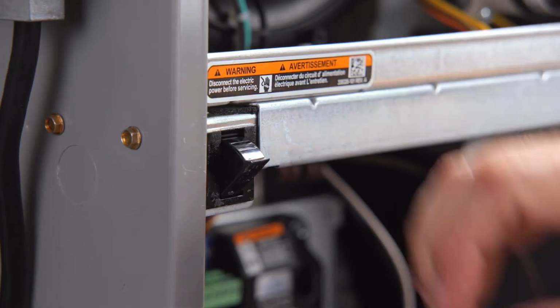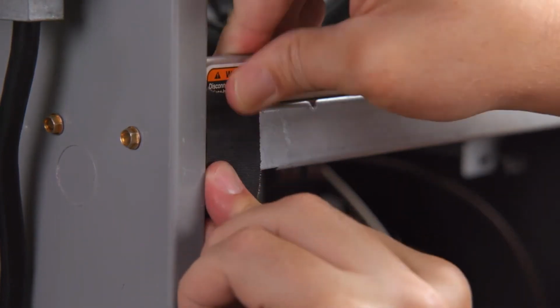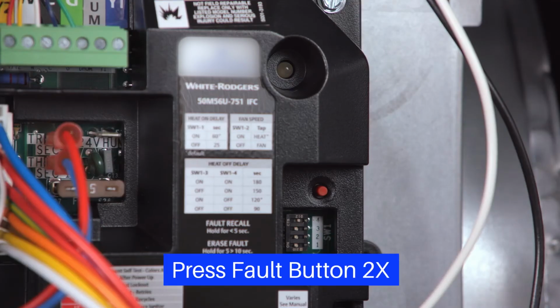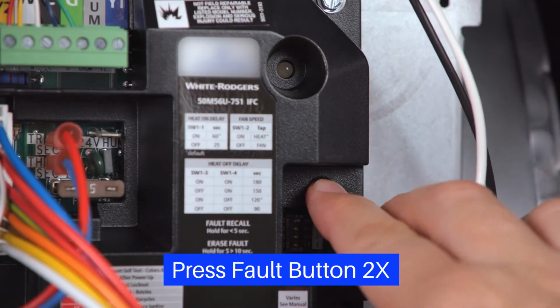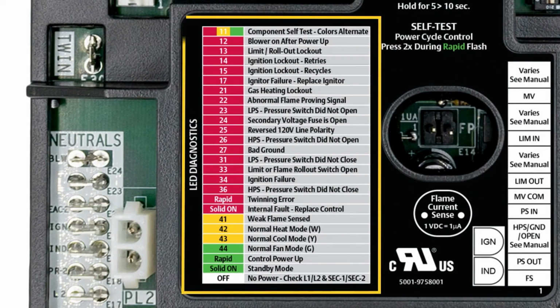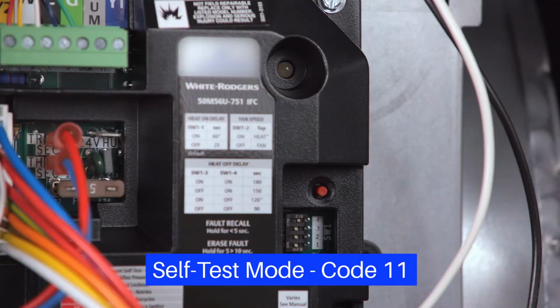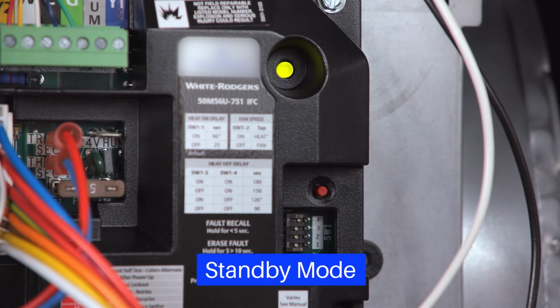To enter self-test mode, turn on power and ensure the door switch is engaged. Press the fault recall button twice within 3 seconds after powering the control while the LED rapidly flashes green. If there are faults, the control LED will flash in red the last stored fault codes 5 times. During self-test mode, the LED will produce one short followed by one long flash, alternating between green, amber, and red, while the control runs the inducer motor, energizes the igniter, and ramps the blower through all available speeds. When self-test mode is complete, the control will enter standby mode and display a green LED.